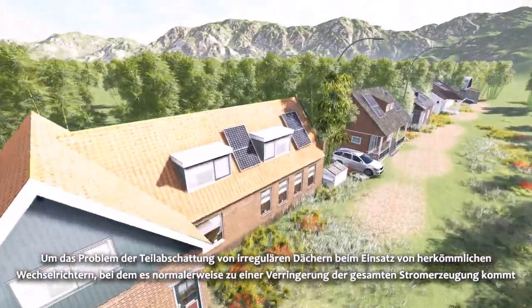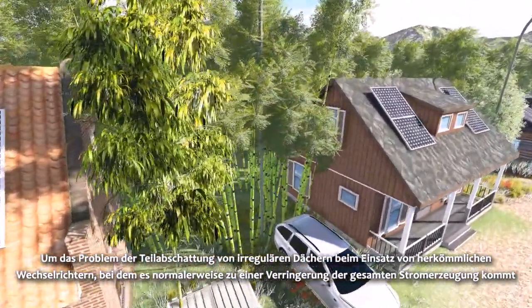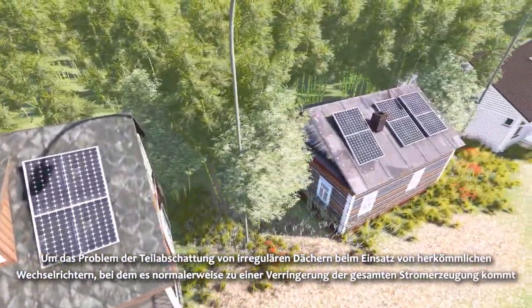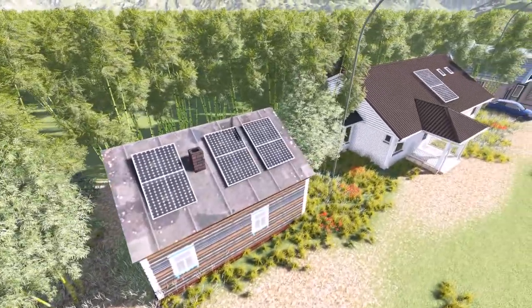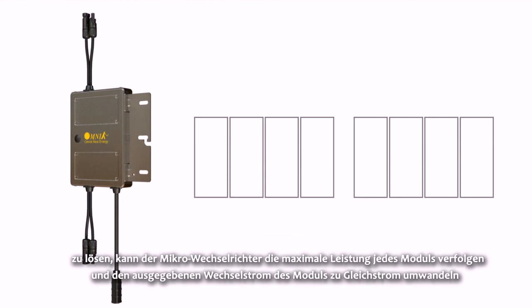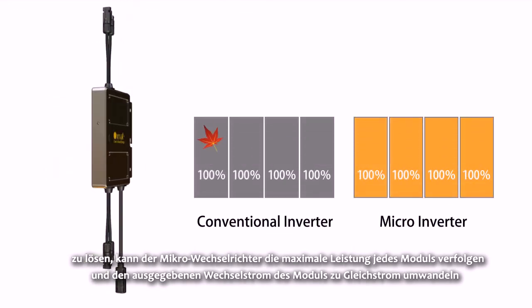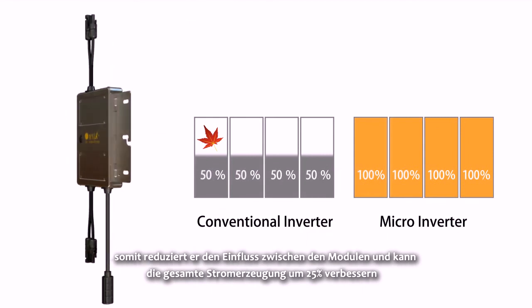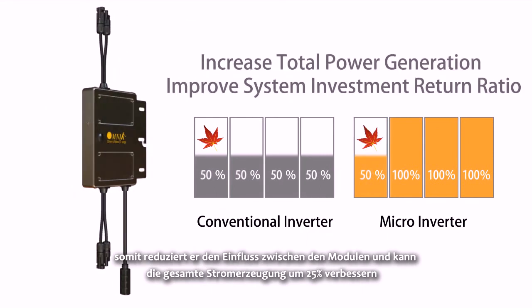In order to solve the partial shading problem of an irregular roof when using conventional inverters — which normally results in a reduction of total generation — the Micro Inverter can trace the maximum power of each panel and directly convert the panel DC output to AC, reducing the influence between panels and improving overall power generation by 25%.